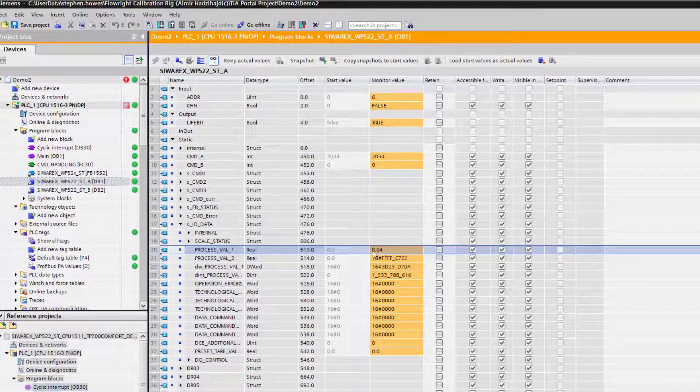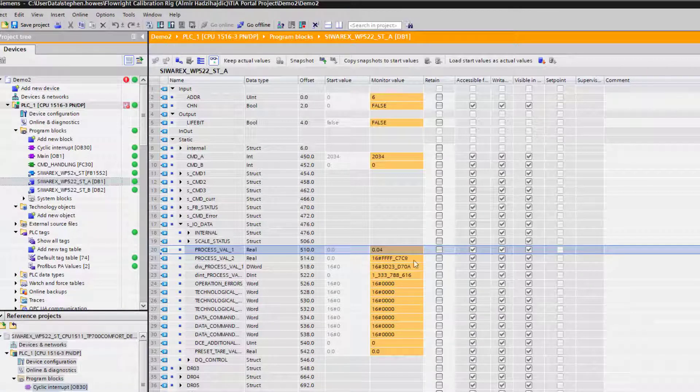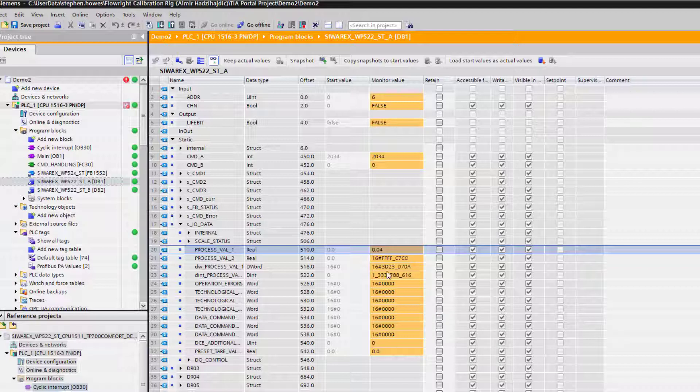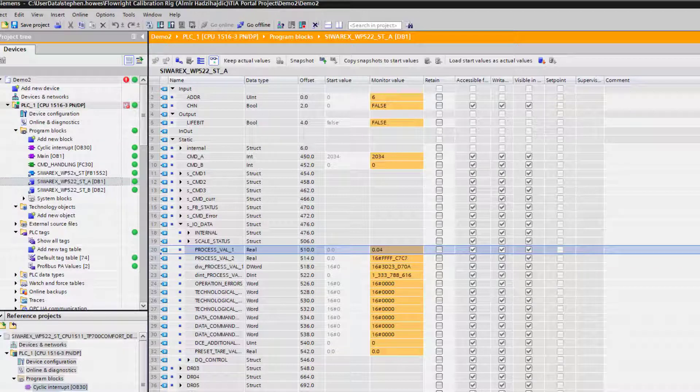We have the real weight. Once you've got to this stage, the SIWAREX is connected, you've got the 24 volts wired up, you've got the load cell connected, you'll be able to squeeze the load cell and see these values changing. We can see the bit toggling so everything is working with regards to the PLC.